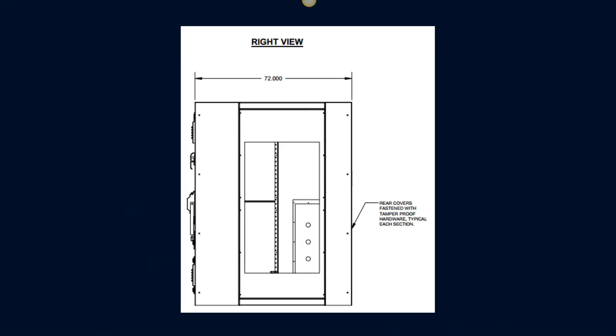The rules governing metal enclosed switchgear are not related to construction. They are only related to testing. And let's look at some ways in which some manufacturers have used this to save cost. So right off the bat, we've gone from 94 inches to 72. So this is still rear connected. This is still 36-inch wide gear, but now we've reduced the depth by taking some of those barriers away to 72 inches. And there's many manufacturers who can do this safely and easily.